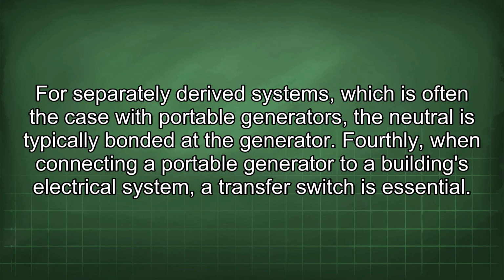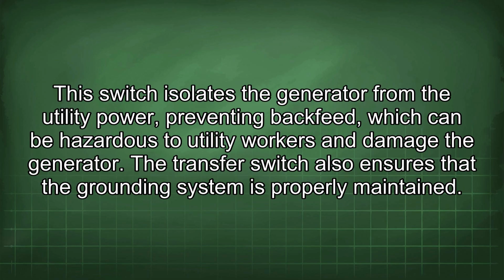For separately derived systems, which is often the case with portable generators, the neutral is typically bonded at the generator. Fourthly, when connecting a portable generator to a building's electrical system, a transfer switch is essential. This switch isolates the generator from the utility power, preventing backfeeds, which can be hazardous to utility workers and damage the generator. The transfer switch also ensures that the grounding system is properly maintained.